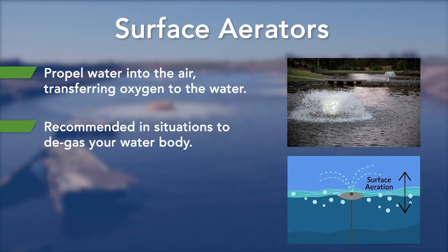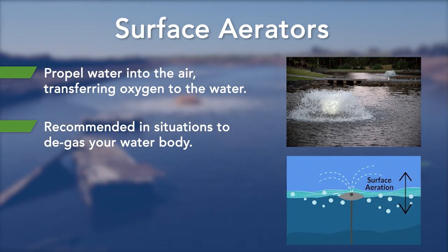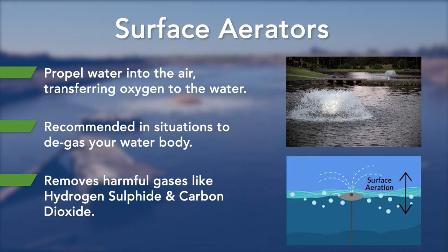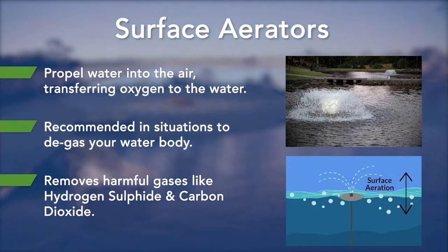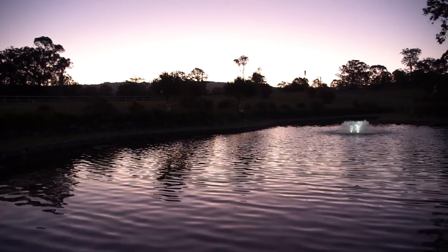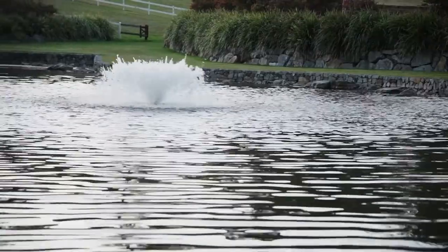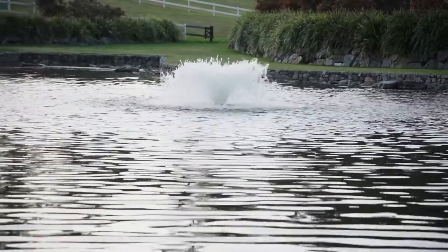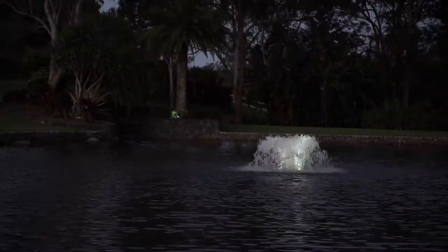Surface aeration is required and highly recommended in all situations where degassing your water body is fundamental. In many applications the removal of harmful gases, which are dangerous for aquatic animals and for the health of the water basin, is far more important than mere water oxygenation. For example, in aquaculture environments a surface aerator is often required to avoid high concentrations of ammonia and CO2, ultimately helping to create a perfect environment for the species being bred.